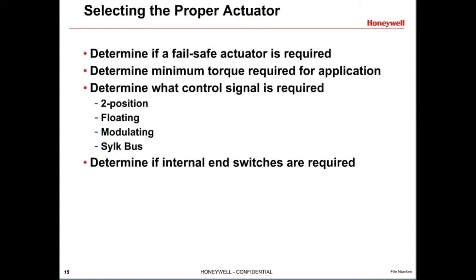To properly select an actuator, there are a few parameters that need to be considered. First, determine if a fail-safe actuator is required for the application. If so, then a spring return actuator is needed. If not, then use a non-spring return fail-in-place actuator. Next, determine the minimum torque required for the application. We will cover this in more detail next.